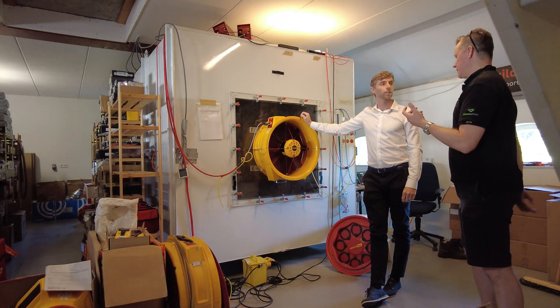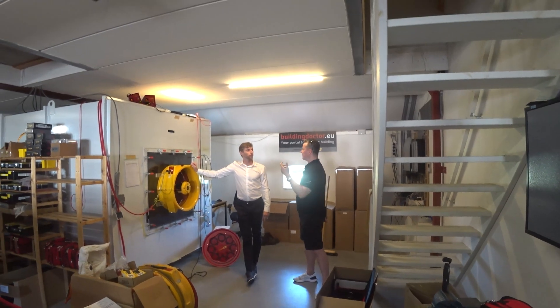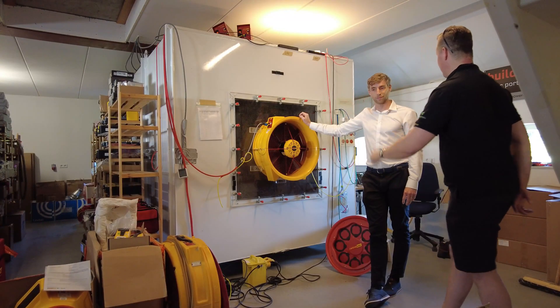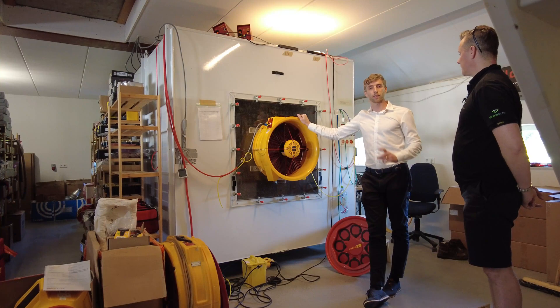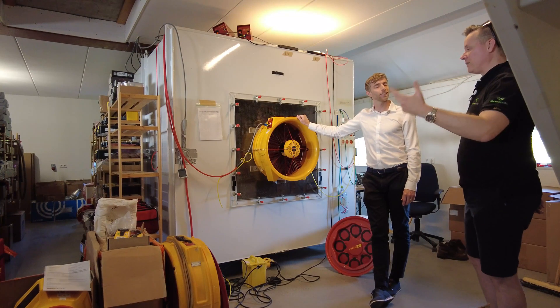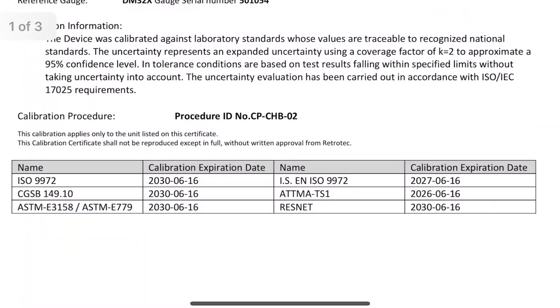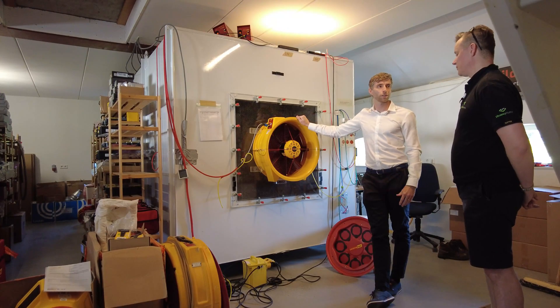The other great thing about Retrotec fans is when it comes to fans being out on job sites and any person checking the calibration of these blower door fans — you guys actually have QR codes where someone can just rock up to the fan and check the calibration information. There's a QR code on the fan, or you can go to the Retrotec website. If you have the new DM32X gauge, the calibration certificate of the gauge is in the gauge itself as well. So there are multiple ways to check if the calibration was accurate — no way of fooling around. Someone can actually check it on site without the airtightness tester knowing. That's good for both parties: a consultant attending as witness can check without the other knowing, and the tester — if asked and without the certificate on hand — it's always there in the database.